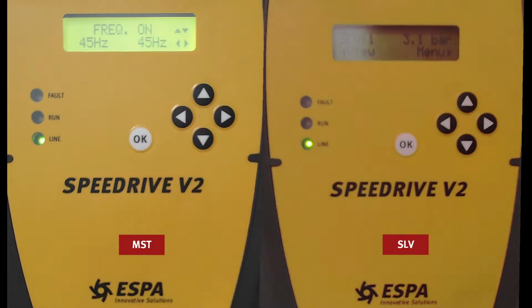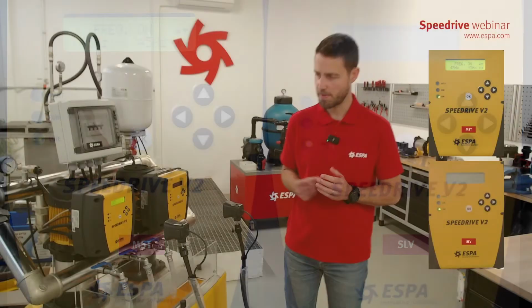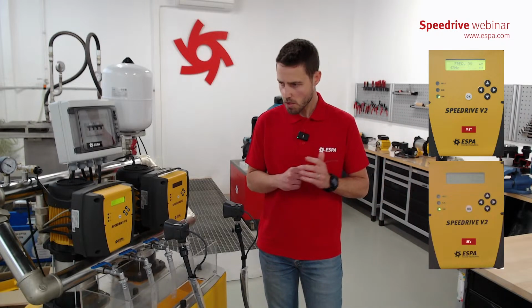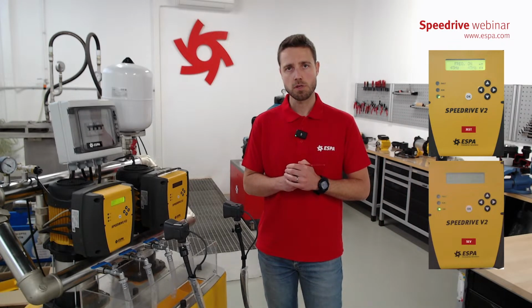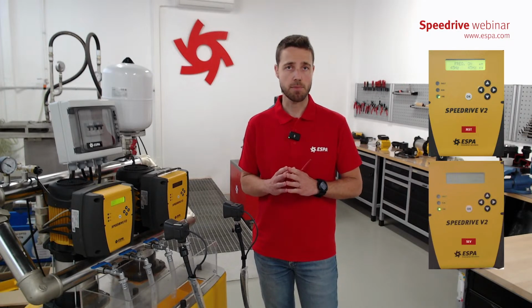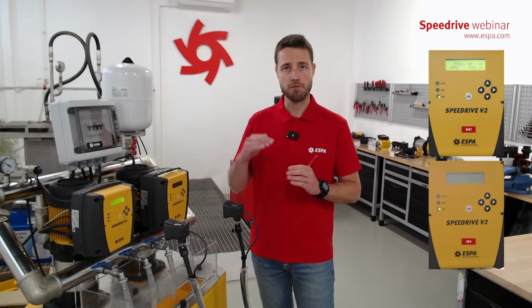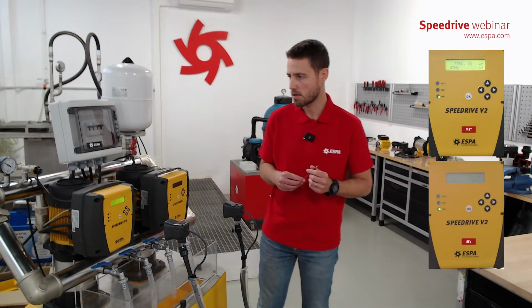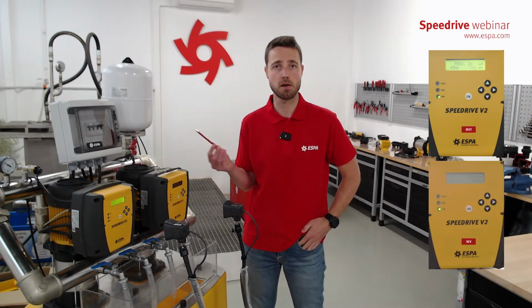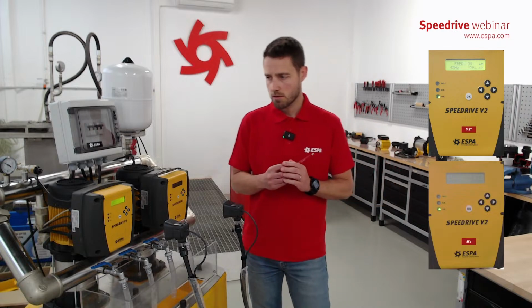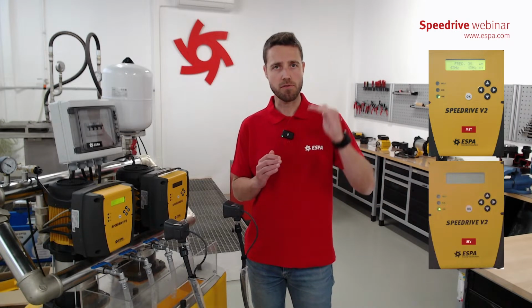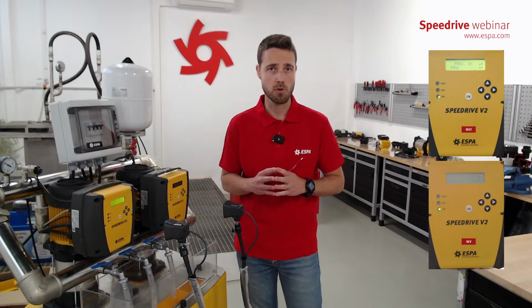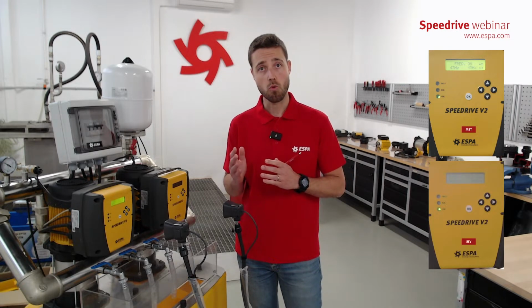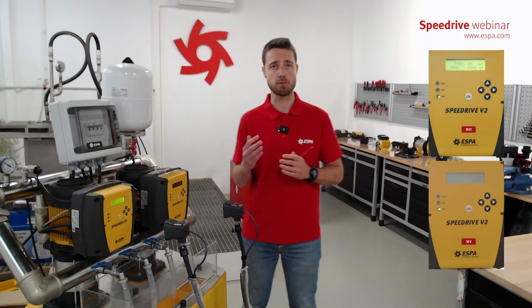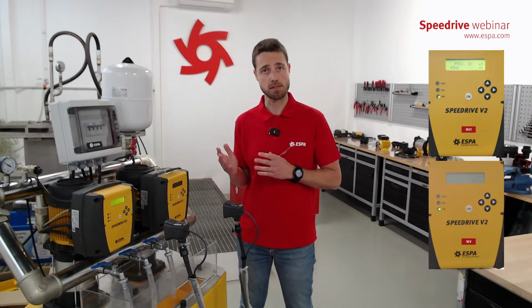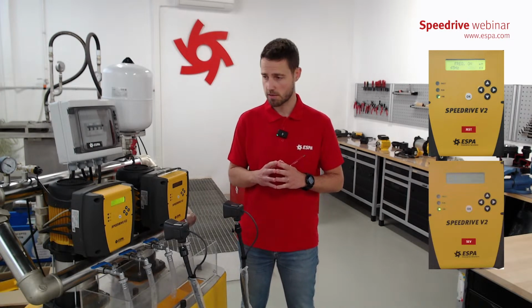Frequency on 45 Hertz. What's the meaning of this setting? You know, the pumps here are set up for working at a maximum of 50 Hertz. This is the frequency that we have from the electric lines. So what's the meaning? When a pump is working at 50 Hertz, it works at its maximum speed. But normally we don't want to reach the maximum speed, because pumps are more stressed, and work better at lower frequencies.